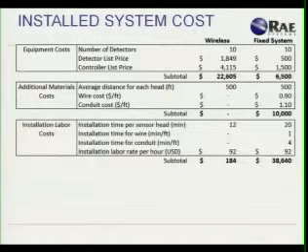We're saying it's roughly 12 minutes per head for a wireless system. That's the time to walk out 500 feet, put a detector out there, then come back. You also have a fixed head. We're saying it's 20 minutes. Where the real difference is, is when you're running cabling and conduit, that takes time to run that type of stuff.